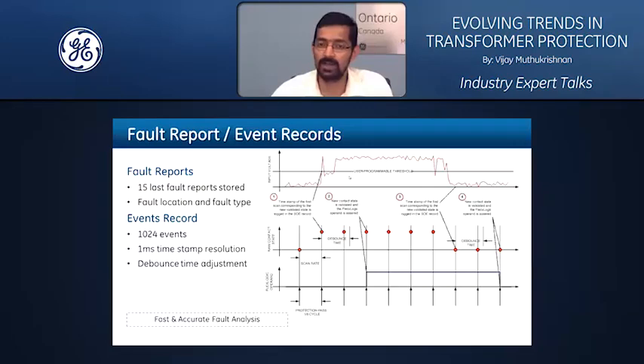And there is the capability, like if you program a debounce timer in order to manage your contact bouncing, the relay should have the ability to backdate the timestamps so that you get to clearly see the first instant that particular contact input got triggered. So these are some fundamental functionalities that can allow you to do fast and accurate fault analysis.